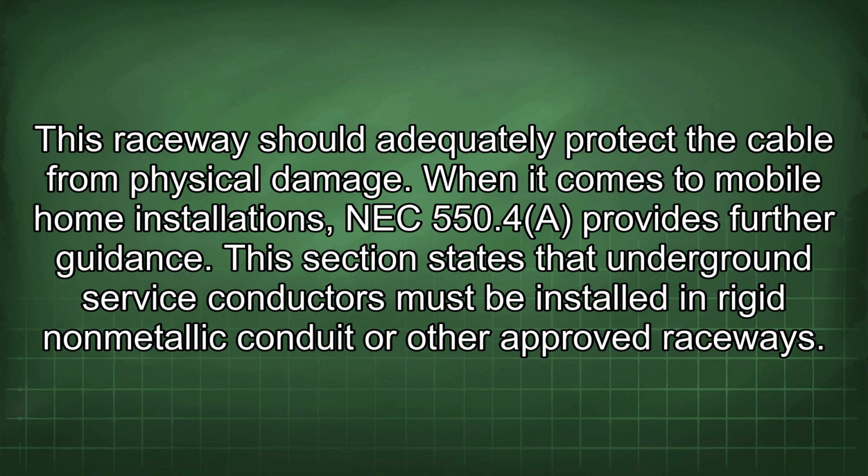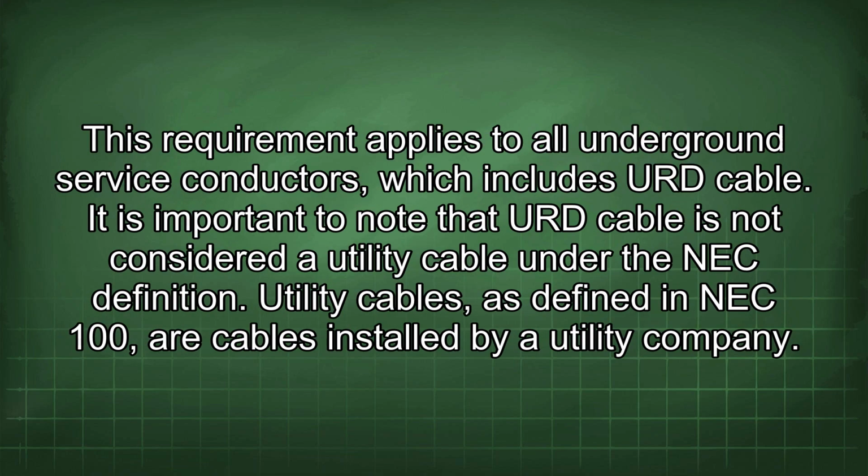When it comes to mobile home installations, NEC 550.4 provides further guidance. This section states that underground service conductors must be installed in rigid non-metallic conduit or other approved raceways. This requirement applies to all underground service conductors, which includes URD cable.